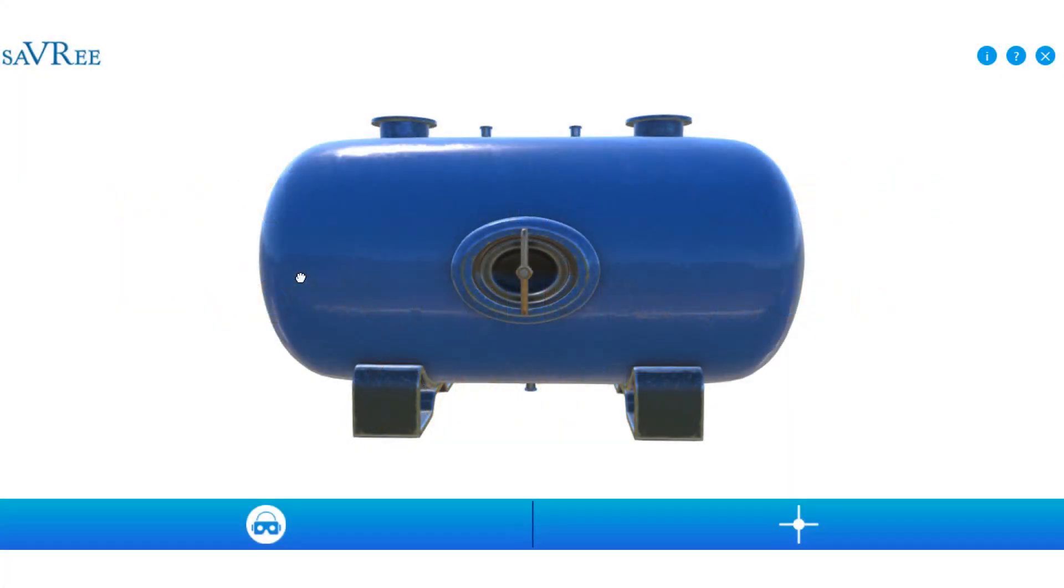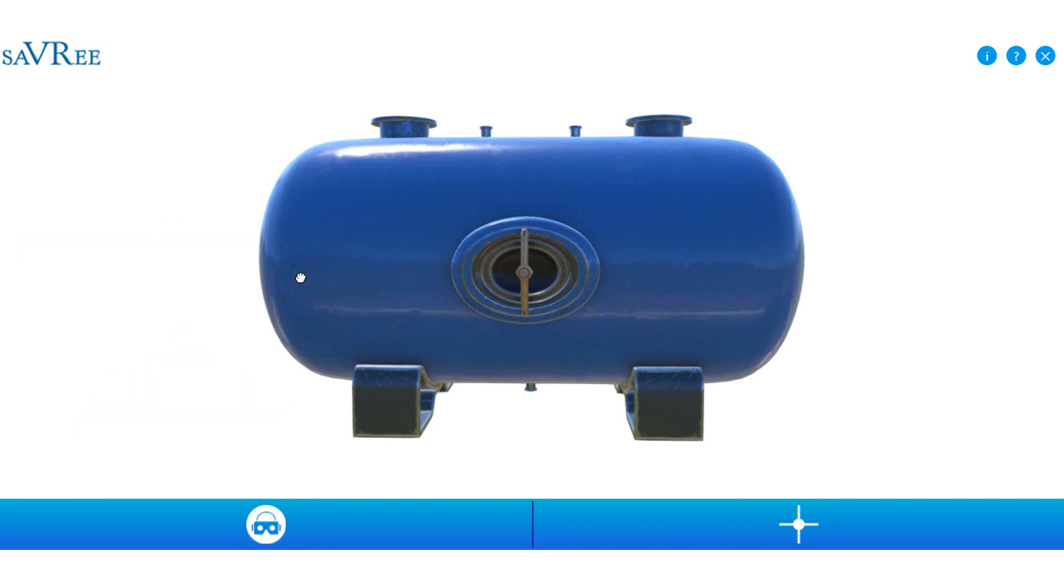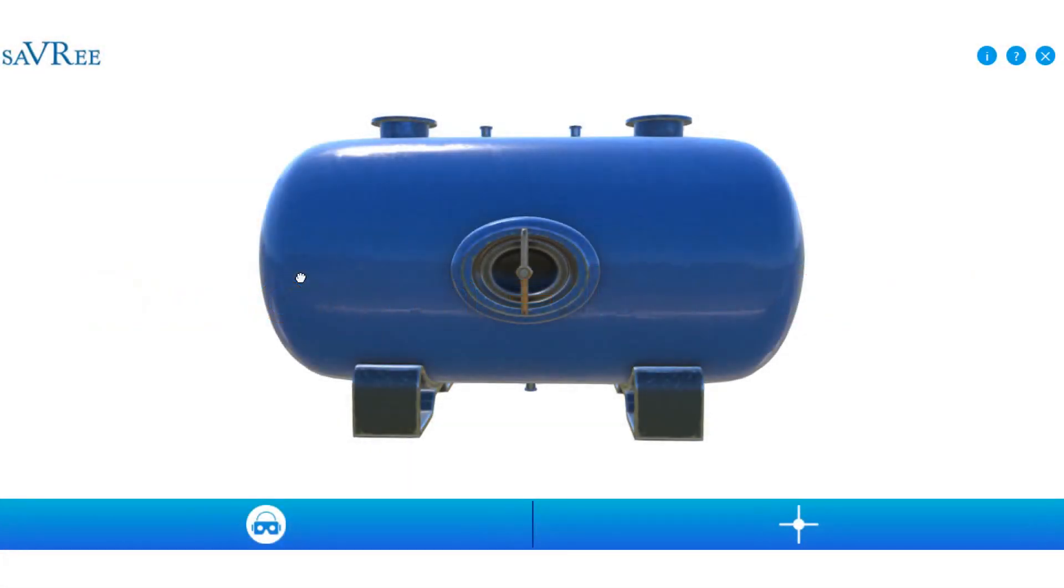The problem is when we have a fire near the pressure vessel. The heat from the fire will heat up the air and this will increase the pressure within the pressure vessel. Now if we cannot release this pressure quickly, we're going to get an explosion.